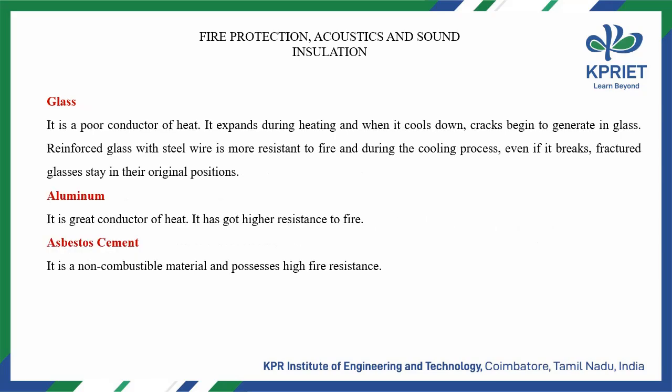Glass. It is a poor conductor of heat. It expands during heating, and when it cools down, cracks begin to generate in glass. Reinforced glass with steel wire is more resistant to fire, and during the cooling process, even if it breaks, fractured glasses stay in their original positions. Aluminum. It is a great conductor of heat. It has got higher resistance to fire. Asbestos cement. It is a non-combustible material and possesses high fire resistance.